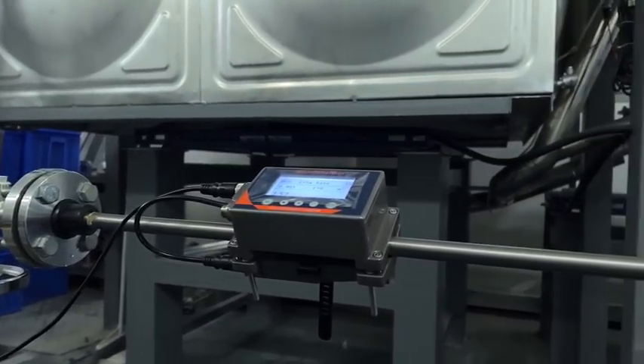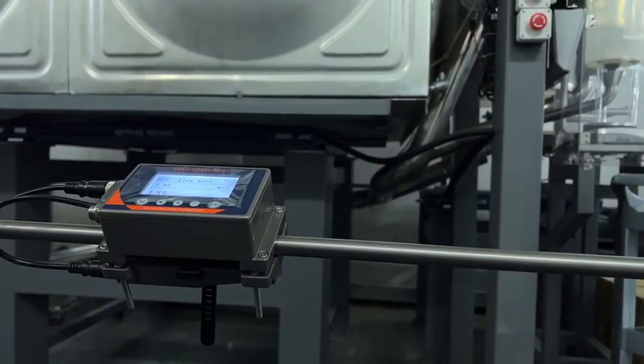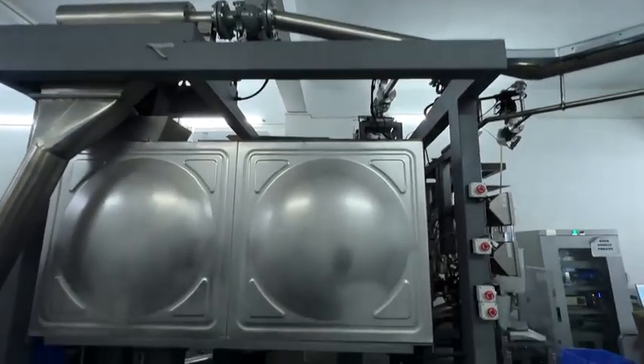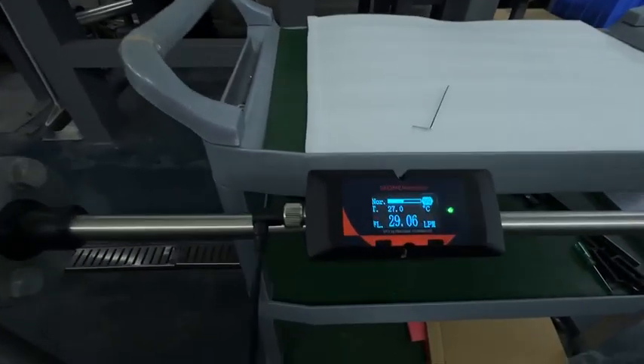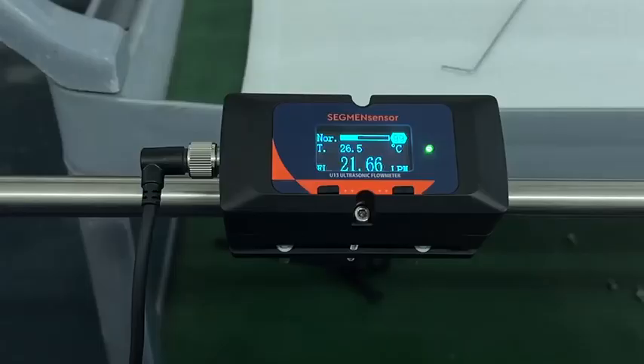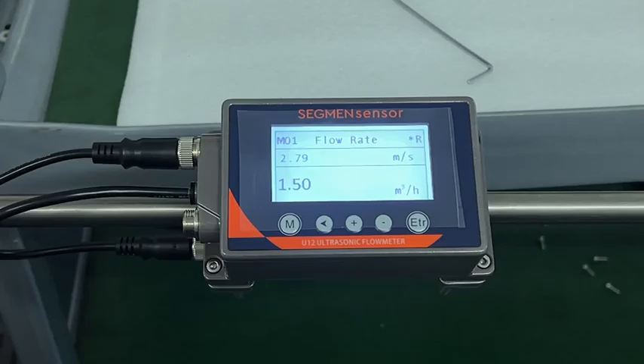Fixed-mount transmitter models go through the same verification process. The unit is clamped to the calibration pipe, parameters entered, and readings verified at multiple flow points to confirm linearity across the full measurement range. For handheld portable models, the same calibration procedure applies. The portable meter is ideal for spot checks, commissioning verification, and troubleshooting across multiple measurement points in a facility. Every SEGMEnSensor ultrasonic flow meter that leaves this facility has passed this complete calibration procedure. A calibration certificate is issued with every unit, documenting the tested flow points, the reference standard used, and the measured accuracy at each point.